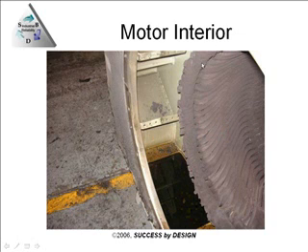And in a medium voltage motor of this size, you have something called a surge ring, which is a rope that goes around to reduce the flexion of the end turns as the motor's running and as it starts up. Because whenever you start up, you have that high current, the windings want to throw themselves at the rotor. So you have all that there in order to reduce the amount of mechanical stress in the motor. For a motor of this size, with end turns this long, and this is, if I remember right, about 15 inches.